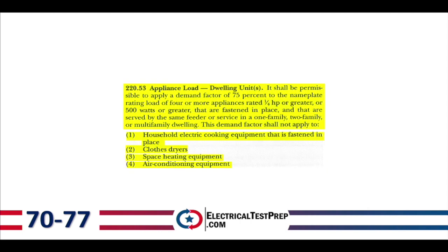Section 220.53, Appliance Loads for Dwelling Units: it shall be permissible to apply a demand factor of 75% to the nameplate rating of four or more appliances rated ¼ horsepower or greater, or 500 watts or greater, fastened in place on the same feeder in a one-family, two-family, or multifamily dwelling. This demand factor does not apply to household electric cooking equipment (Table 220.55), clothes dryers (220.54), space heating equipment (100%), or air conditioning equipment (100%).